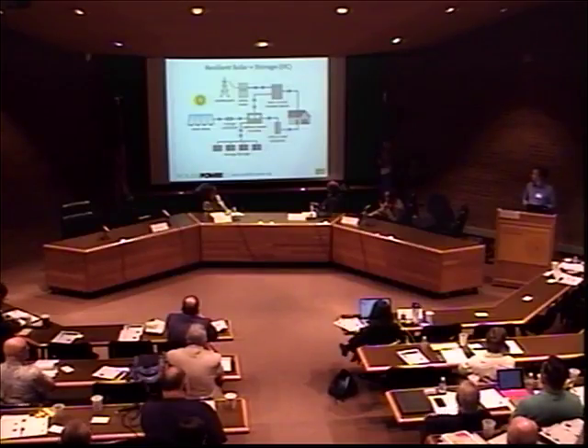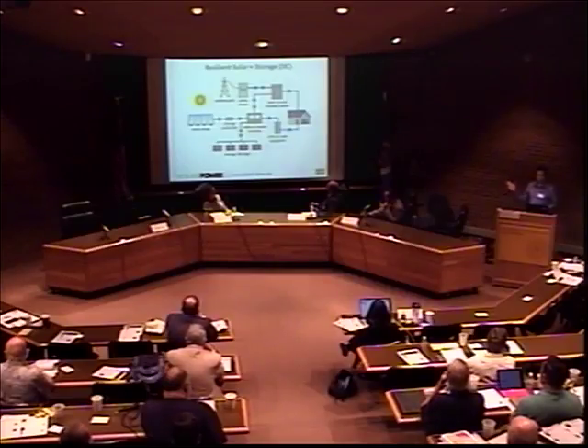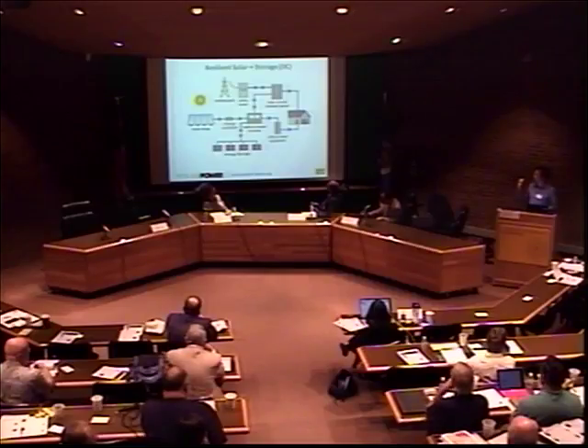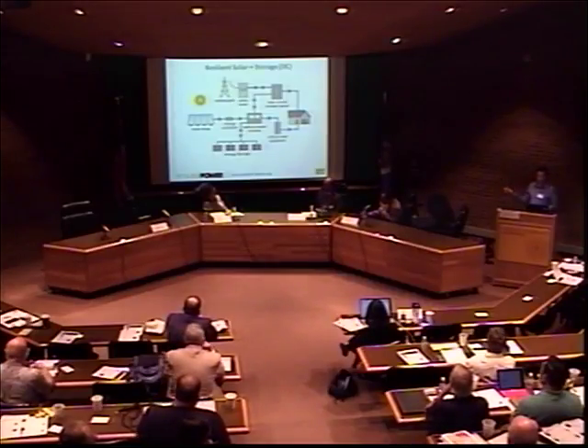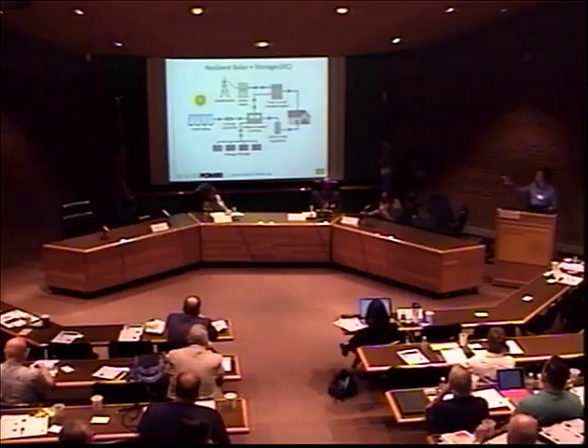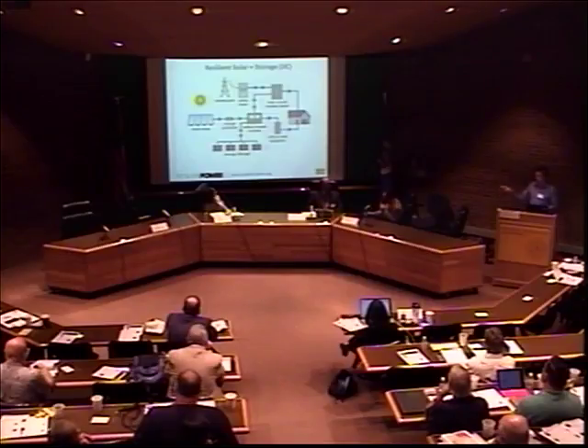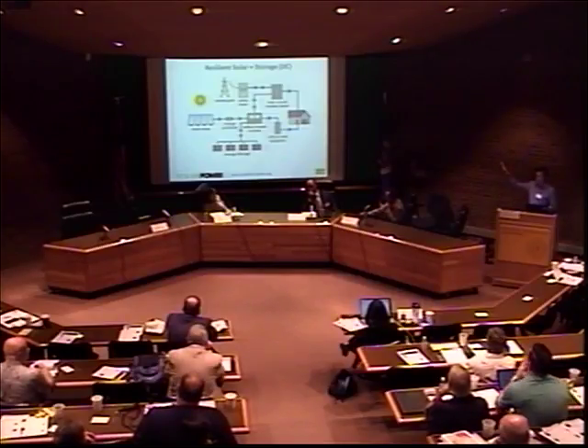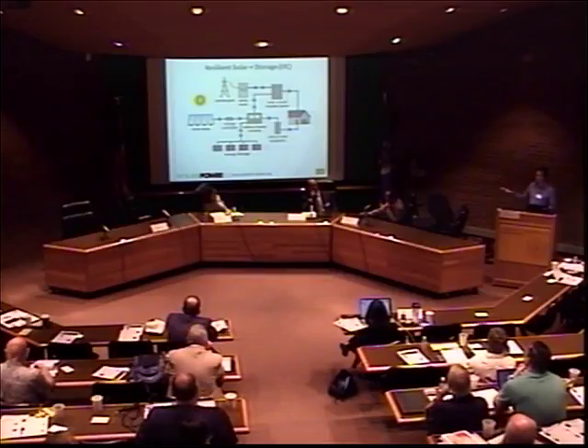So the battery-based inverter is one change. The other change is this critical load subpanel. The critical load subpanel takes the loads that you want to support through your solar and storage system when the grid is unavailable. That top part, the central grid, utility meter, main circuit panel, when the grid's not there, all of that gets disconnected from the system tied into the facility. Everything else continues to work the way it was working before.